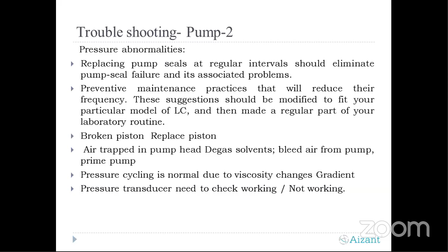When we are preparing or selecting a mobile phase, we also have to check the viscosity of those solvents. During mixing of the solvents, the viscosity will change, and pressure cycling will be different if there is not proper mixing. There is a pressure transducer in the HPLC system. If it's not working, you will not identify that the pump is not working properly. So I can say it's a monitor which gives the ECG of your HPLC pump. So we have to periodically check whether the pressure transducer is working properly or not.